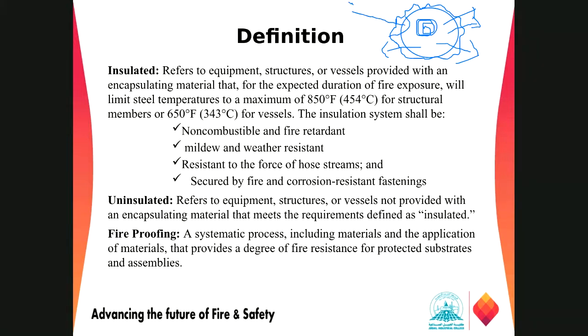It's for equipment, structures or vessels provided with an encapsulating material that, for the expected duration of fire exposure, will limit steel temperature to a maximum of 454 degrees Celsius, right? And for vessels we have 343 degrees Celsius. So the idea is just to insulate the surface so that heat from the outside will not come and affect our equipment.